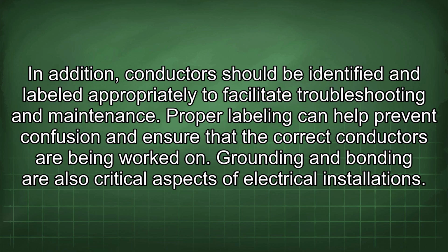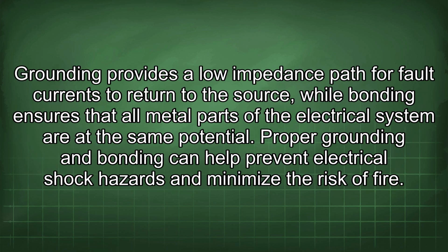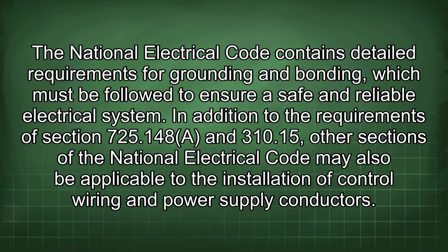Grounding and bonding are also critical aspects of electrical installations. Grounding provides a low impedance path for fault currents to return to the source, while bonding ensures that all metal parts of the electrical system are at the same potential. Proper grounding and bonding can help prevent electrical shock hazards and minimize the risk of fire.